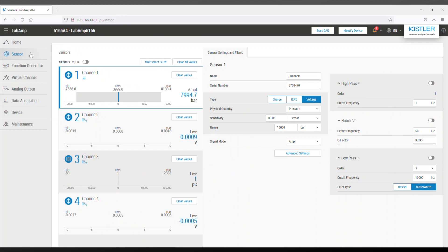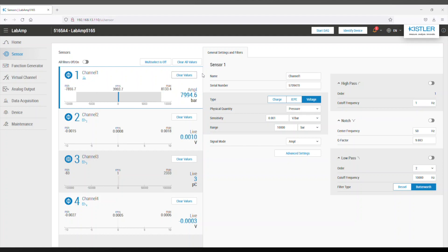Best is to wait a few seconds before reading the amplitude. As you can see, our amplitude reads 7994.6 bar. This is very close to our expected 8000 bar and I can now go use my 5018 with peace of mind.